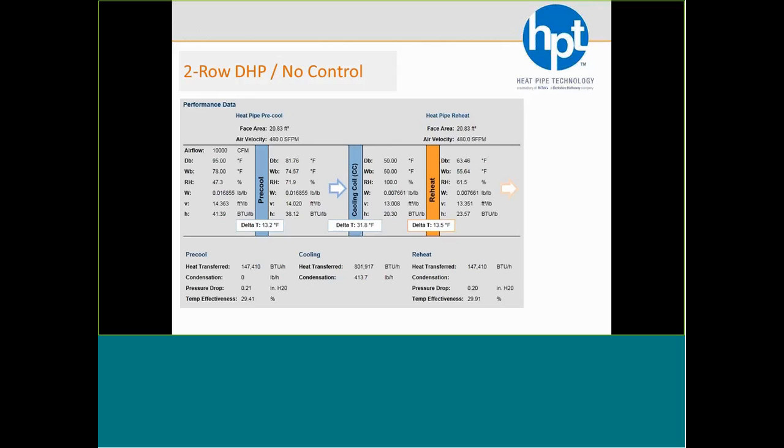But yeah, if we want to get up to 65, well then we're underperforming. And yes, you could leave it as is. You're never going to get too hot, and you're never going to have to worry about controlling it, and you are good to go. But if your focus is to save as much energy as possible, well then you're underperforming because you're not taking advantage of the fact that you can reheat up to 65 degrees all the time.